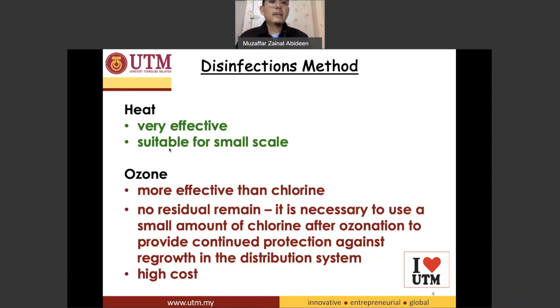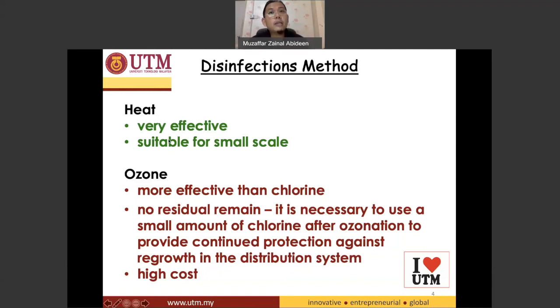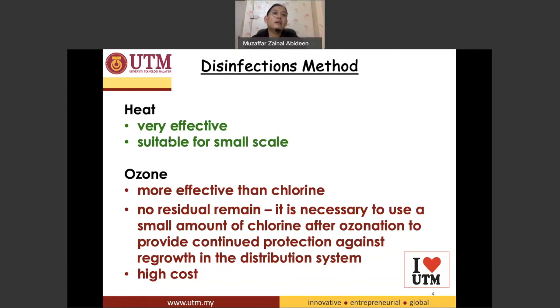Heat is not suitable for a bigger size water treatment plant. Another disadvantage of heat is there is no residual effect. We need to have some residual disinfectant in the water system, and it's not possible to heat up all along the pipe during distribution of water. So that is the first method — heat.